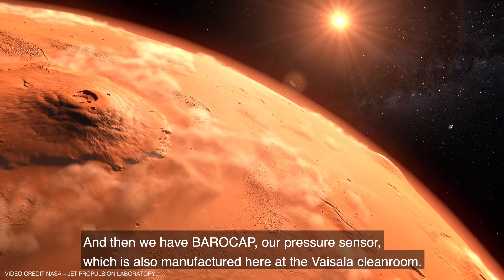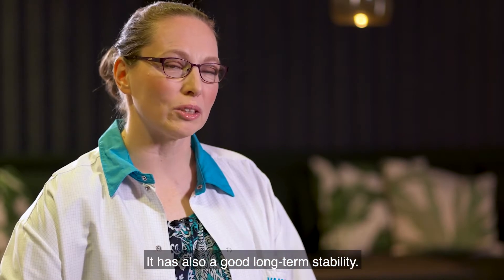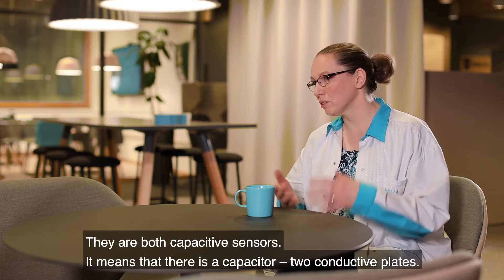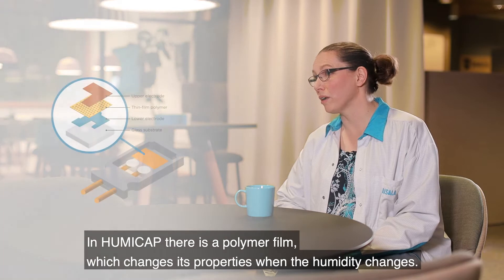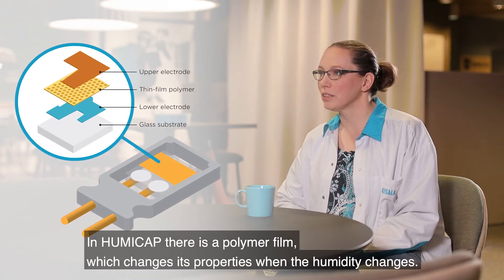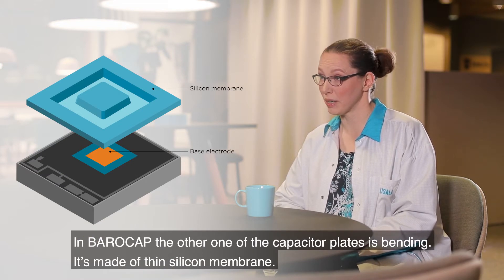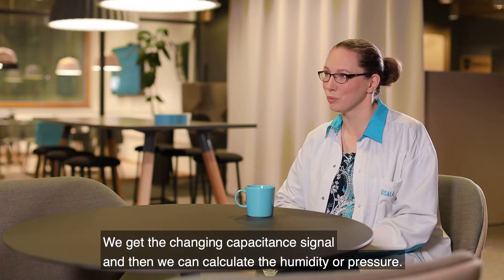And then we have BAROCAP, that's our pressure sensor. It's also made here at the Vaisala clean room and it has a good long-term stability. They are both capacitive sensors, meaning there's a capacitor — like two conductive plates. In HUMICAP there's a polymer film in between which changes its properties when the humidity changes, and in BAROCAP one of the capacitor plates is bending, made of a thin silicon membrane. So we get a changing capacitance signal from which we can calculate humidity or pressure.